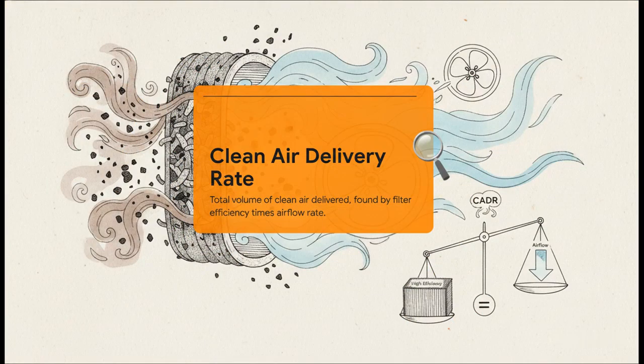Okay, so now that we have fresh air entering the building, we have to filter it. And there is a massive misconception in the industry regarding filter efficiency that we are going to debunk right now. To fix it, you have to master CADR, the Clean Air Delivery Rate. CADR is simply the total volume of clean air a system can deliver. You calculate it by taking the filter's efficiency and multiplying it by the airflow rate. This simple equation anchors a totally critical mechanical trade-off in building science.